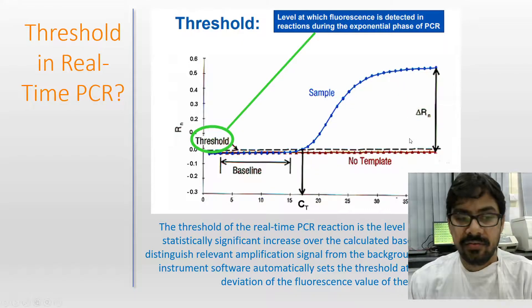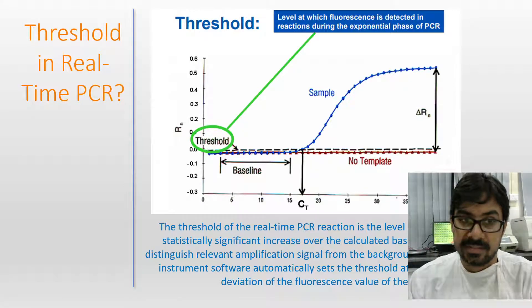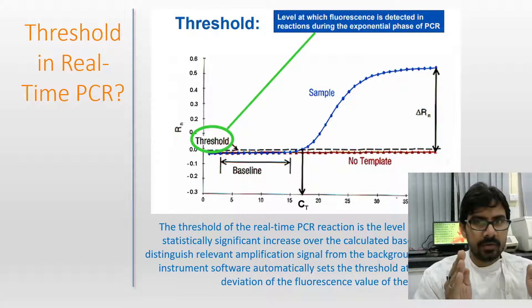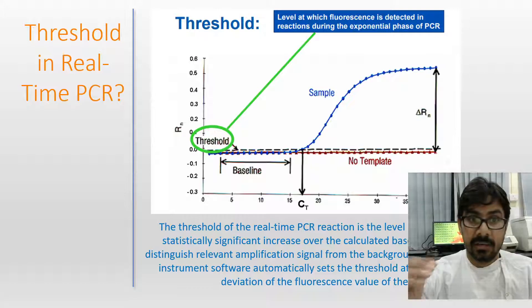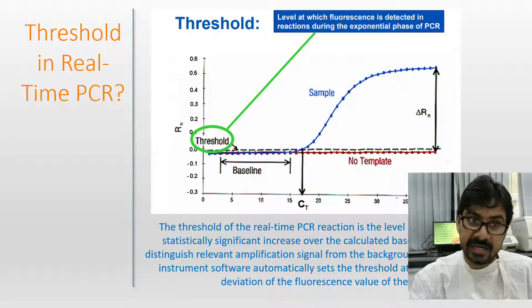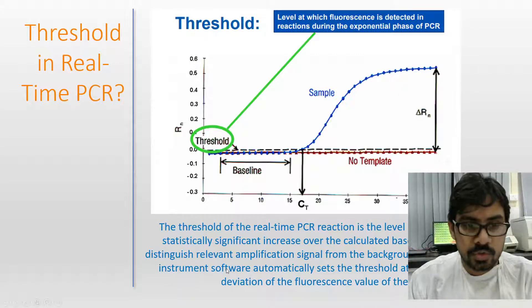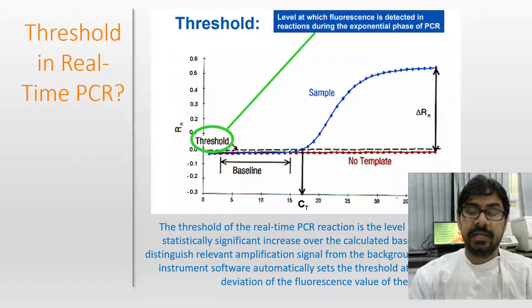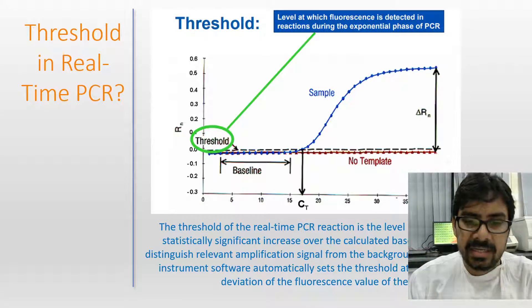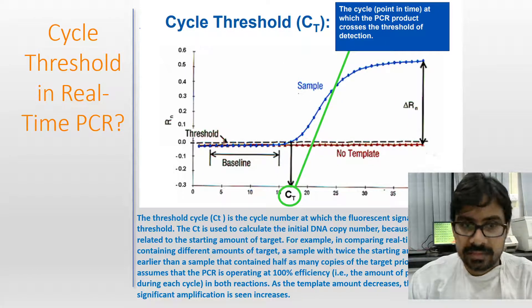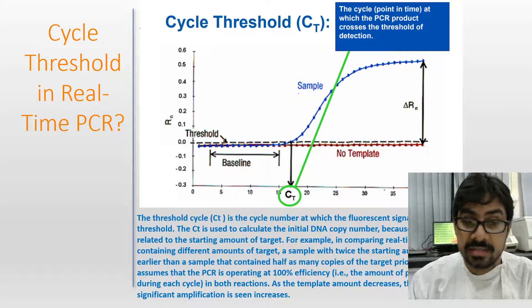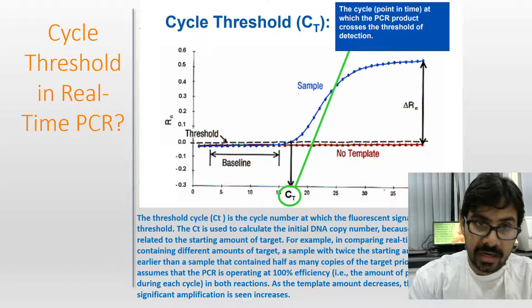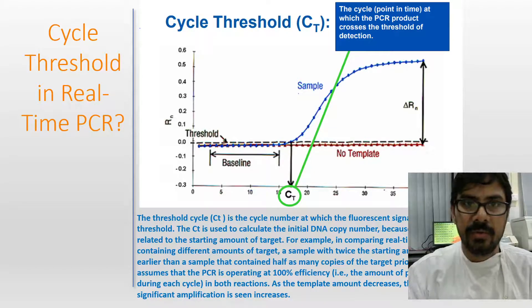The threshold in real-time PCR is the level of signal that reflects a statistically significant increase over the calculated baseline signal. It means amplification has started but hasn't yet reached a significant level — once it crosses that significant level, the Ct comes into picture. The real-time PCR instrument software automatically sets the threshold — you can adjust it after getting results — typically at 10 times the standard deviation of the fluorescence value.